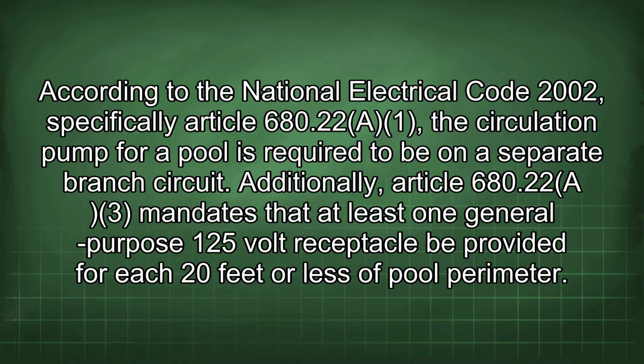According to the National Electrical Code 2002, specifically Article 680.22(A)(1), the circulation pump for a pool is required to be on a separate branch circuit. Additionally, Article 680.22(A)(3) mandates that at least one general-purpose 125-volt receptacle be provided for each 20 feet or less of pool perimeter.